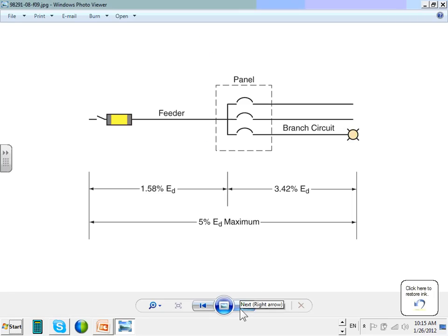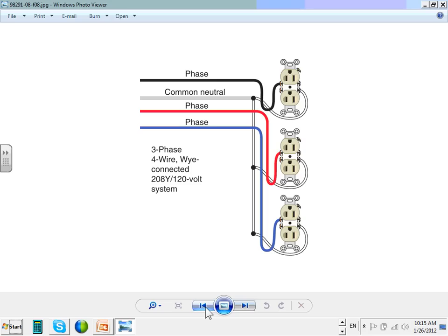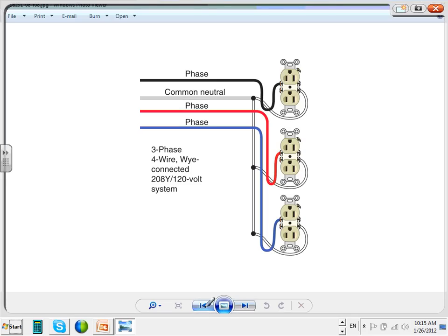Okay, any questions, guys, about the harmonics? I promise you we'll come and visit the harmonics a little bit later as we go through. Number 10, what about the pigtail, number 10 at the junction and the box holding the receptacles? Very good point. If you pull number 10, do they have an overcurrent protection device ahead of them? No. Because the neutral doesn't land on a fuse, I can tap it with a conductor equal to the load, which is probably number 10. But if it's not landing on an overcurrent protection device, you can argue that you don't have to do that.